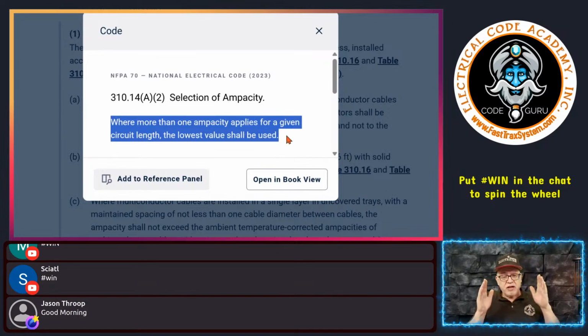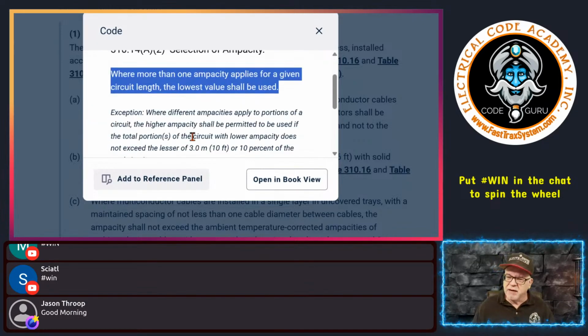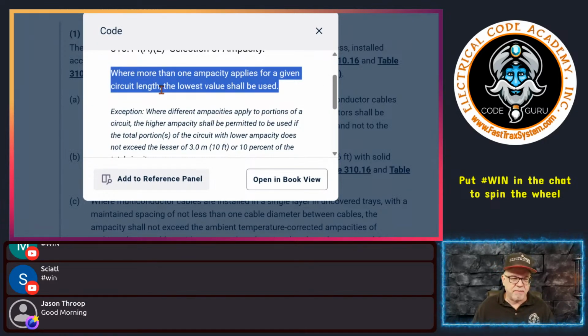In our case, it would be if we were using the ampacity based on the conductor, but we had to reduce it so that it doesn't exceed 95% of the ampacity of the table, then that is a lower value compared to the portion of the conductor of the cable that isn't underneath the cover. Well, if that's the case, you would go with the what? You would go with the ampacity that's then up to 95%, right? But then you have this allowance here.